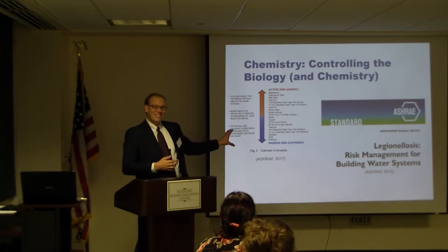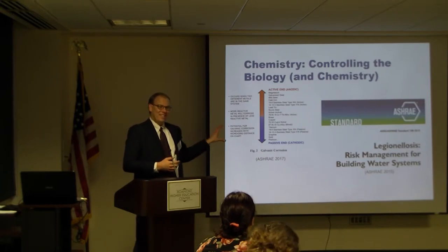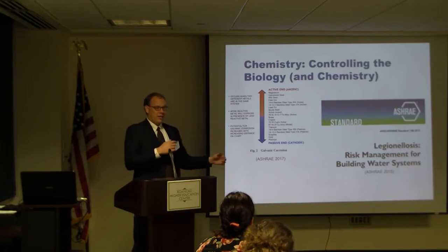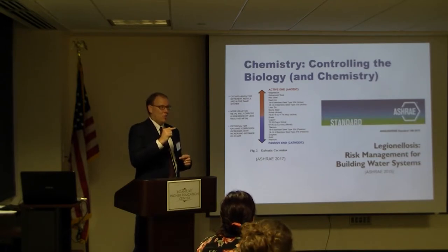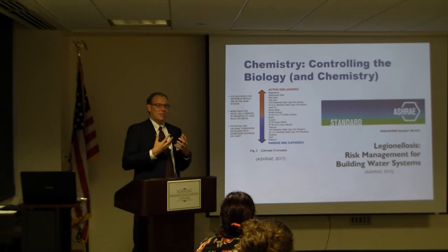The whole point of this conversation is Legionella comes from cooling towers and unmanaged water sources. Bacteria likes to grow between about 70 degree water temperature and 140 degree water temperature. If you don't manage the bacteria that's growing in that range, and you have to operate in that range, cooling towers always operate in that range, you will get biological diseases in the air.